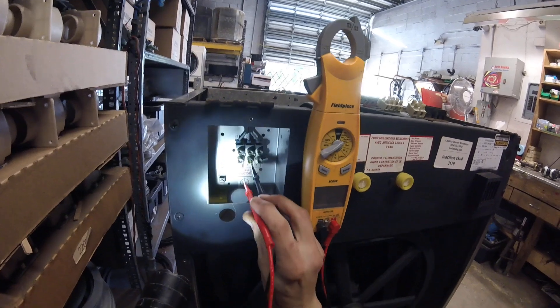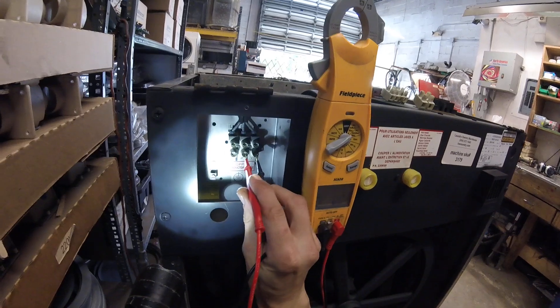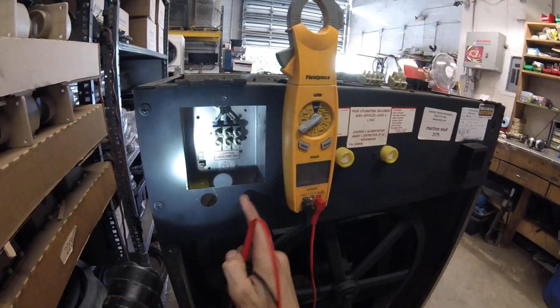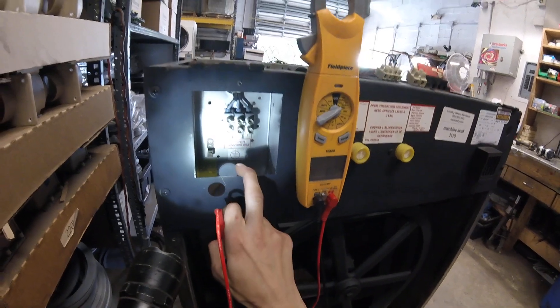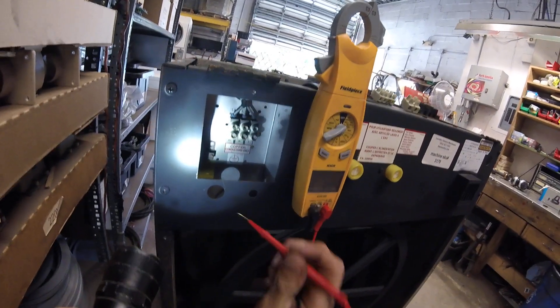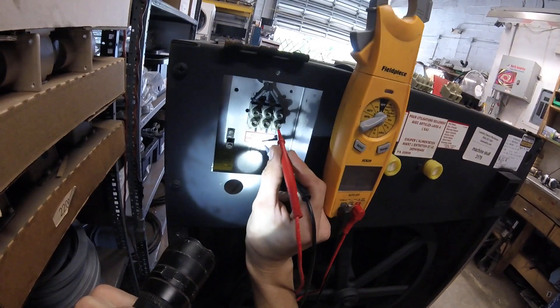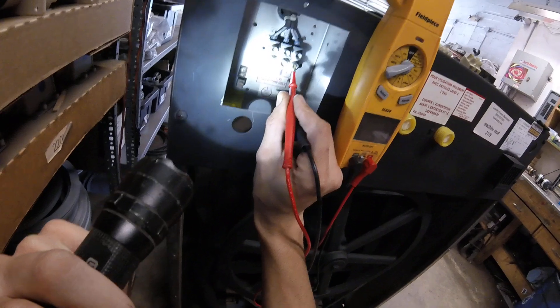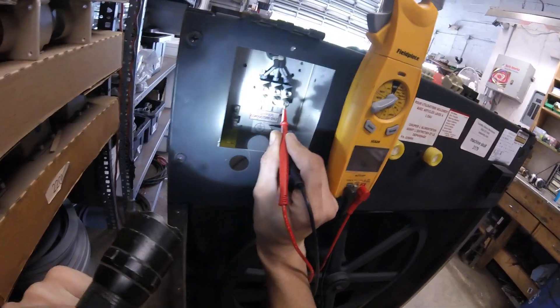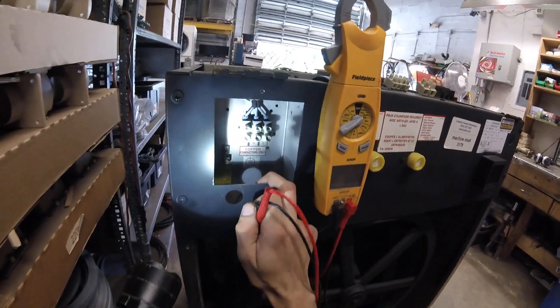When you read across L1 and L2, you should be getting 220. Same with L2 to L3. So individual legs to ground: 120. Legs jumped across should be 220. If you have one leg that by itself you're reading 220 when you jump it to ground, you might be running a phase converter. Instead of getting your third phase from the power company in that case, just make sure that your 220 leg is on L3, not on L1 or L2.